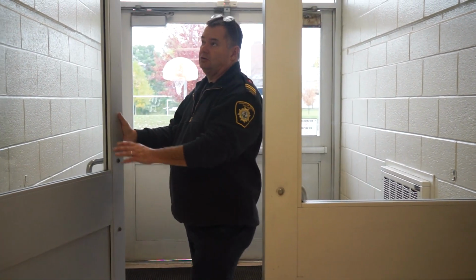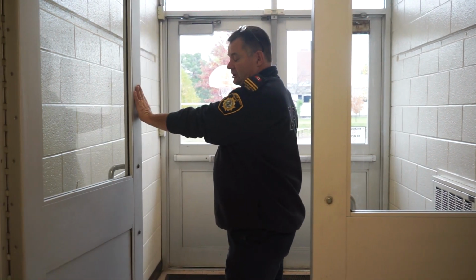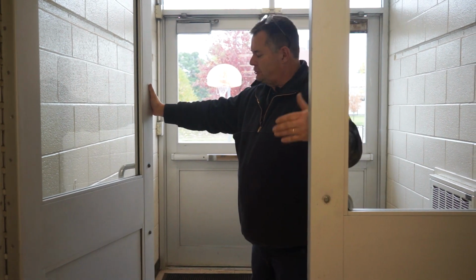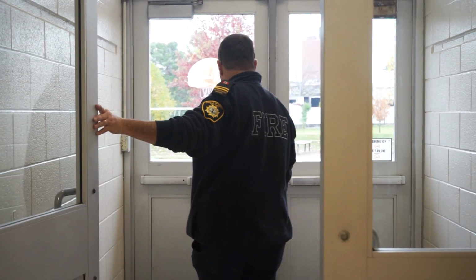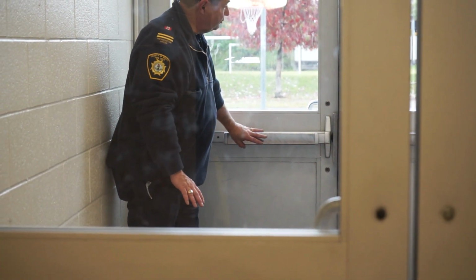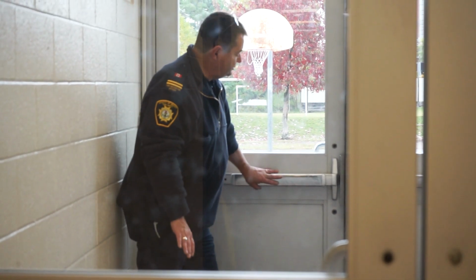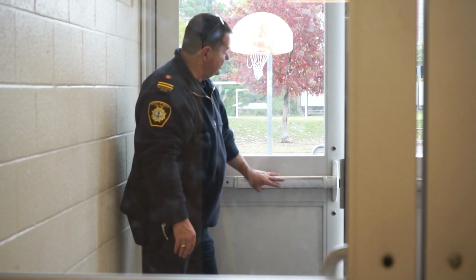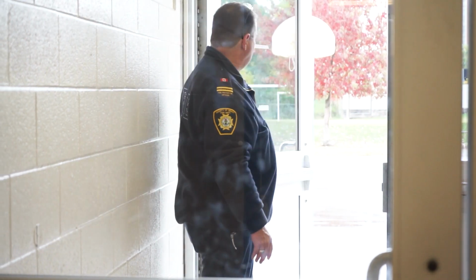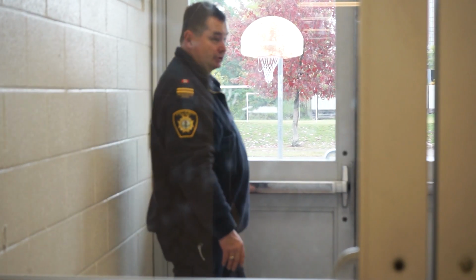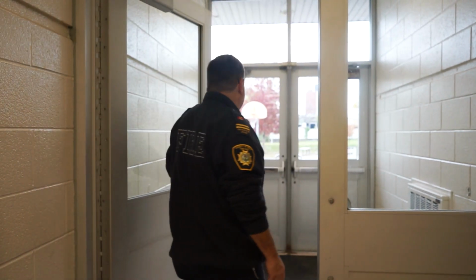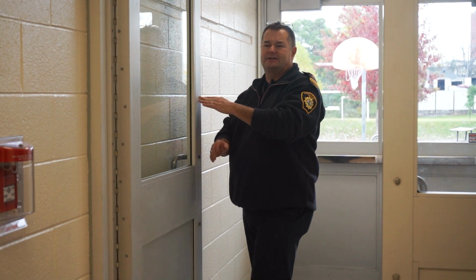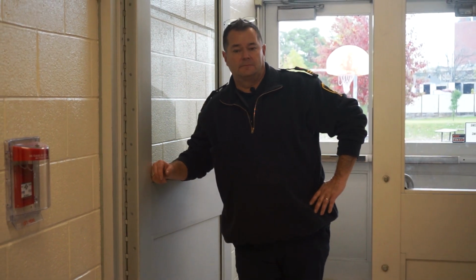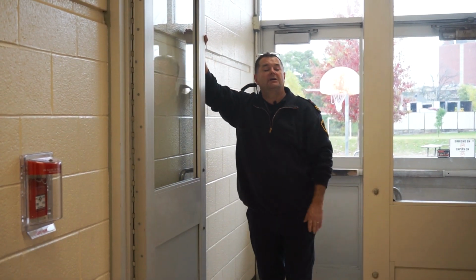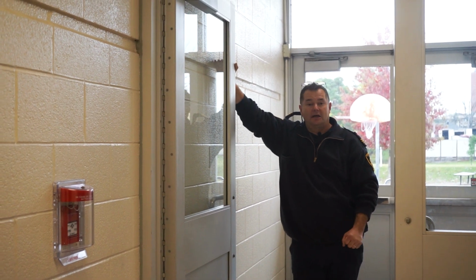The difference between this door is this is just a pass-through door, meaning it's not locked, there's no kind of locking device on it. It is just a temperature control door. But the exterior doors are met with panic hardware, which allows the door to be locked, but when we need to get out, it unlocks the door and it unlocks in the direction of travel. And we open the door, walk through the door, let go of the door, it resets the lock, and then the door closes. We can't use anything to hold the doors open. The only way we can hold the door open against the closer is there's a component that comes with our fire alarm system. It's called a magnetic hold open device. And when that's placed on the door, it is allowed to be held open, because once the fire alarm is activated, then it will allow the door to close.